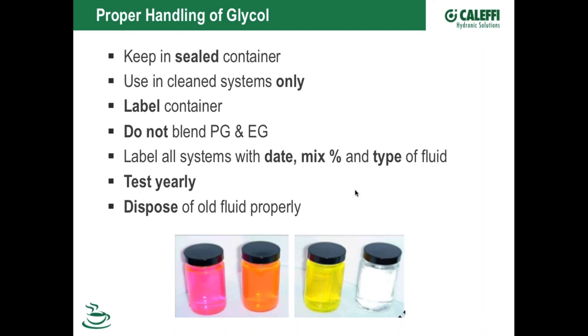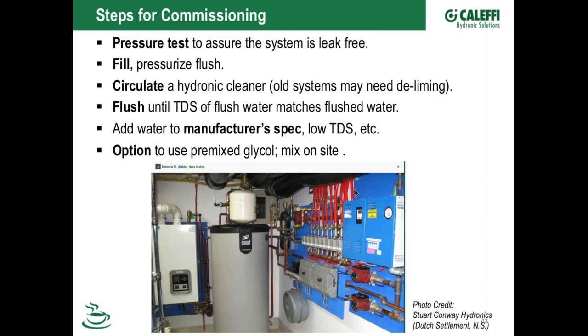Here's what I want you to do: pressure test, fill and pressurize, and circulate a cleaner through an old dirty system. Flush it out until the TDS of the fluid coming out matches the fluid you're putting in. Then put your glycol in the system, either pre-blended or mixed on site with good water. When you leave the job, put a sticker on the boiler or system with a note on what you did, the glycol mix percentage, your name, the pH you left it at, and the date. That way if another technician goes back years later, he'll know what's in the system.